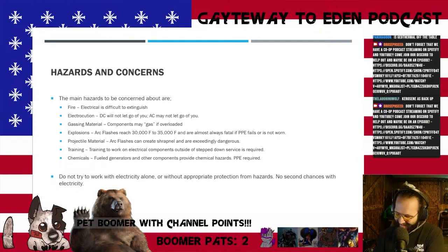Explosions - arc flashes can reach 30,000 to 35,000 degrees Fahrenheit and are almost always fatal if the PPE fails or is not worn. This is correct ANSI-rated PPE, also colloquially termed the B suit. It has to be in date as well - if it's out of date, throw it out and get new ones. And if it fails or has so much as a little scratch, get rid of it, it's compromised.